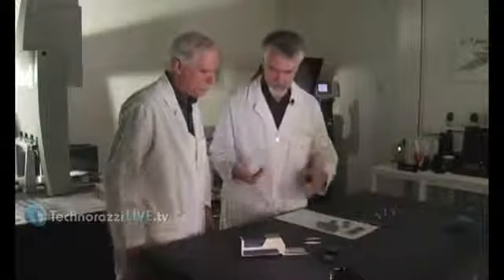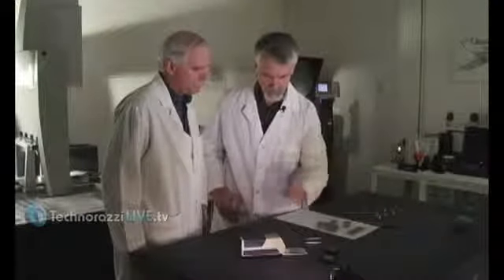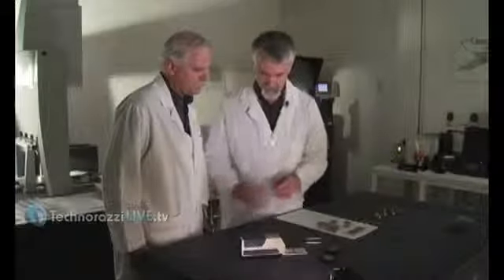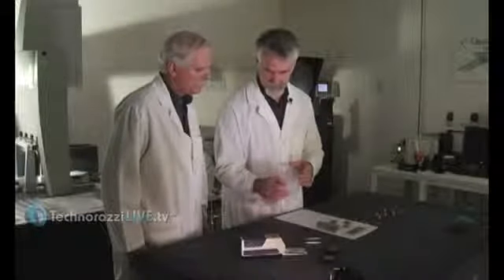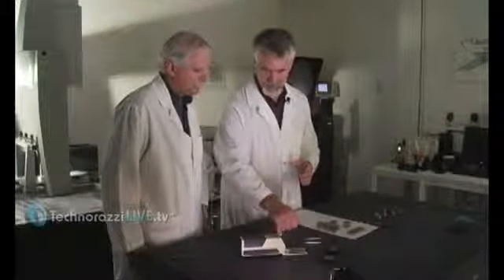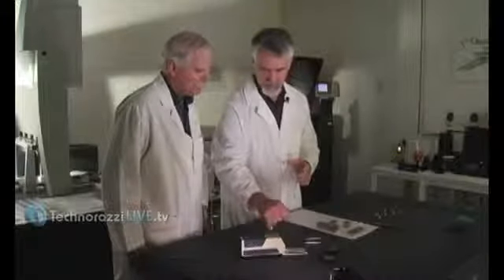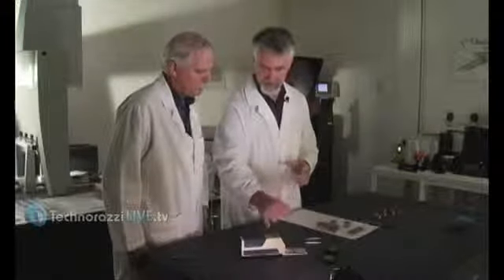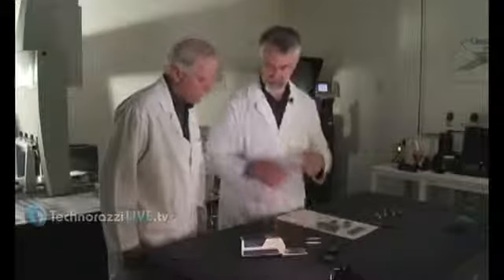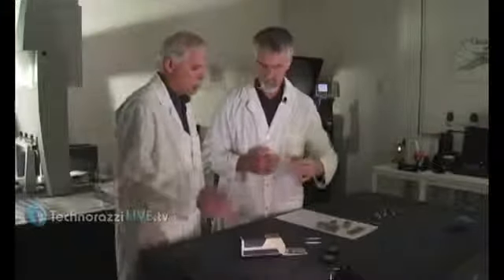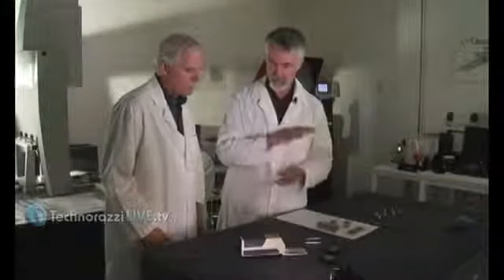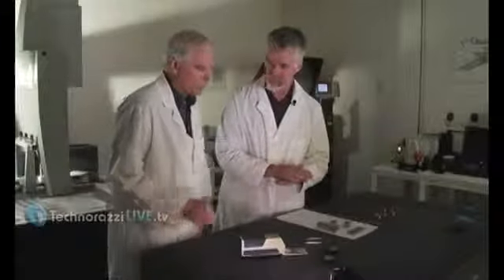So the process then, if I understand this right, is you put your reference standard in there, you take a measurement, and you adjust the gain so that what's showing up on the display matches what the reference standard says it's supposed to be. Yes, now you're set to go. And then you can put your material under test. Then you would put the part to be measured.